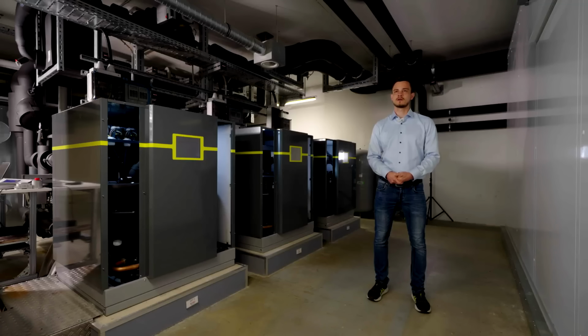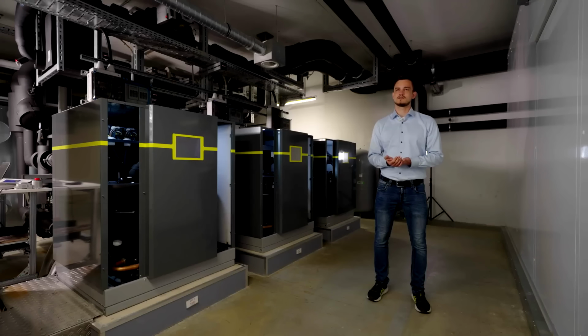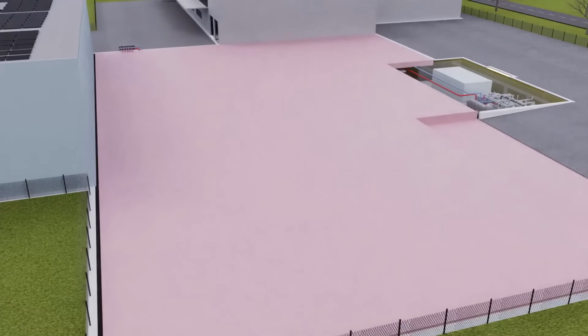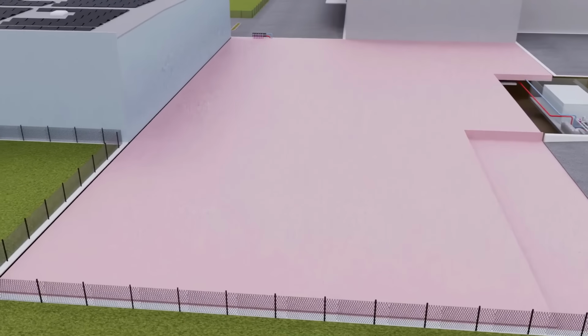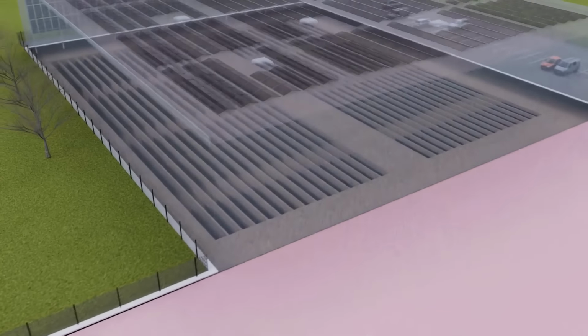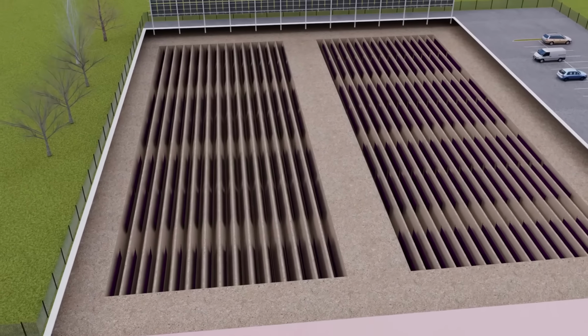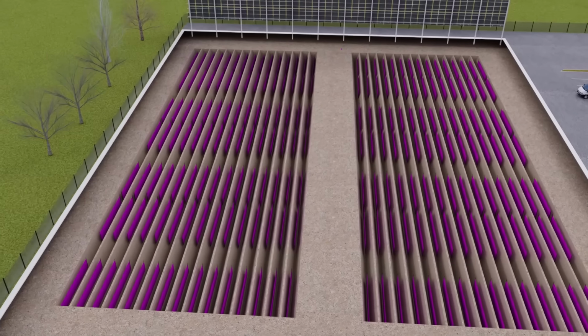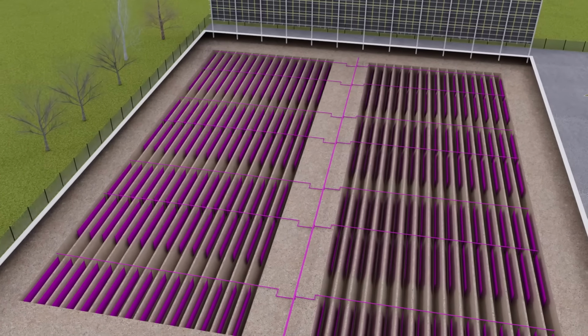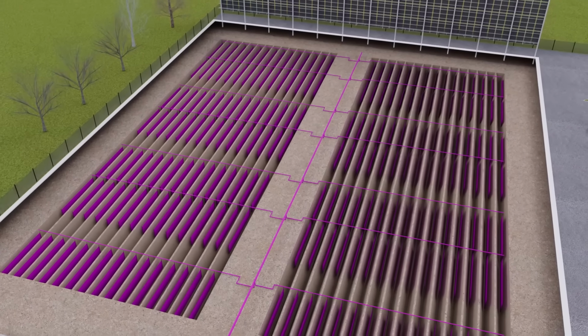Thanks to the smart control system of the heat pumps, the concrete core can be overcharged with heat. When we know the sun will be shining and the temperature high, we let the heat pumps run for an extended period. We overcharge the concrete core, raising the temperatures higher than usual. Thanks to the storage capacity, we can use this energy a week later when we need it and avoid having to turn on the heat pump at a time when it would be less efficient. If the sun does not shine for a few days, the heat pump nevertheless doesn't need to run because the concrete core is still warm enough. However, if the sun doesn't come out for several days, and the outside temperature drops below 2 degrees Celsius, the ground collectors now supply heat for the building. By the end of winter, the ground storage system has a temperature of 5 to 10 degrees Celsius.